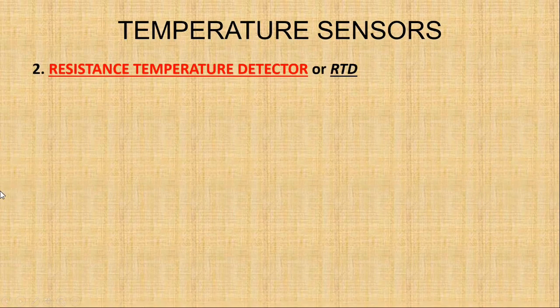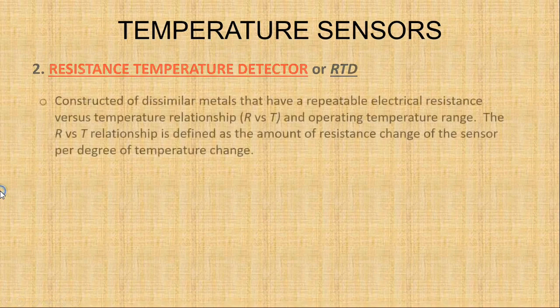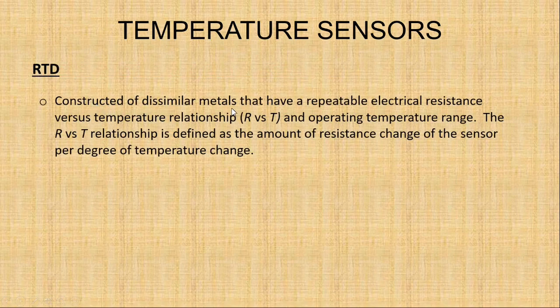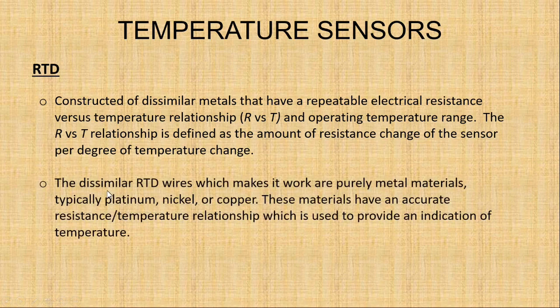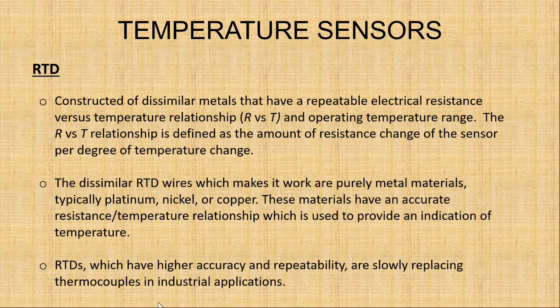The next type of sensor is the RTD. RTDs are constructed of metals that have a repeatable electrical resistance versus temperature relationship and operating temperature range. The R versus T relationship is defined as the amount of resistance change of the sensor per degree of temperature change. The RTD wires, which make it work, are purely metal materials, typically platinum, nickel, or copper. These materials have an accurate resistance-to-temperature relationship, which is used to provide an indication of the temperature. RTDs, which have a higher accuracy and repeatability, are slowly replacing thermocouples in industrial applications.